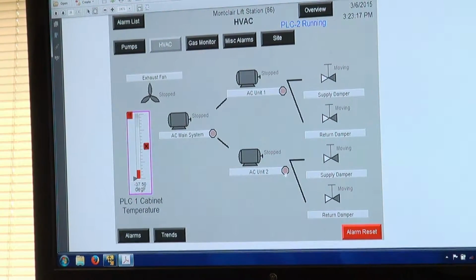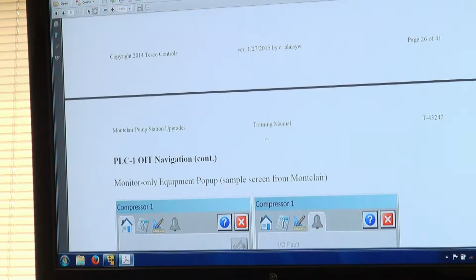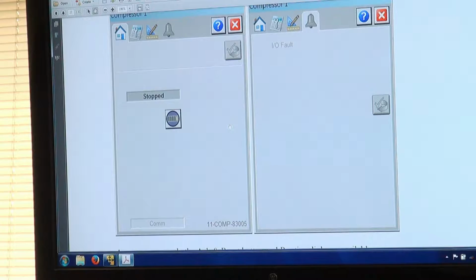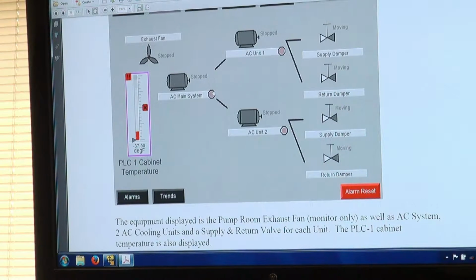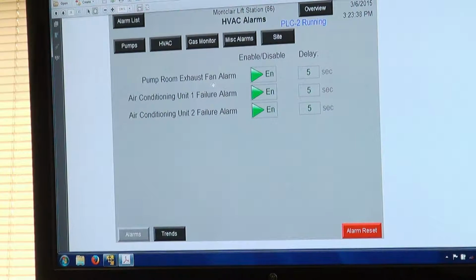We don't have the auto on any of these 3, so that's why there's an interlock associated. When you pop open these, it doesn't show the interlock because there's no controls. All you can get to is the runtime. It's not a great thing, but I can't do anything about it. This is a Rockwell issue. But just realize that looking at this screen, you do see that there's something wrong with the device itself. If the exhaust fan is not running, there's an alarm. We don't have the not running, but both of those units have alarms associated with them. So you would be able to see if you have a failure with one of the 2 units, not just that it's powered off.